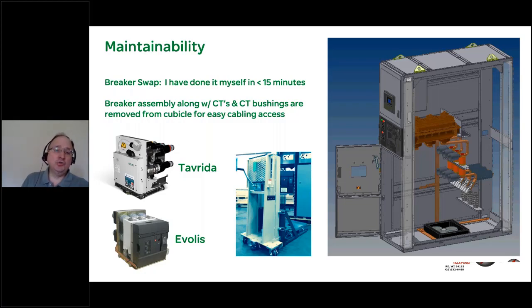If you do choose a fixed mount breaker, I can tell you I have done it myself. I've removed a breaker and put in a replacement breaker in less than 15 minutes. So certainly fixed mount is an option, even in process environments. Because again, I have the isolation switch above with insulated bus, compartmentalized, where I've isolated, locked out, tagged out, and have load side grounding with that switch. It's a switch over breaker design.